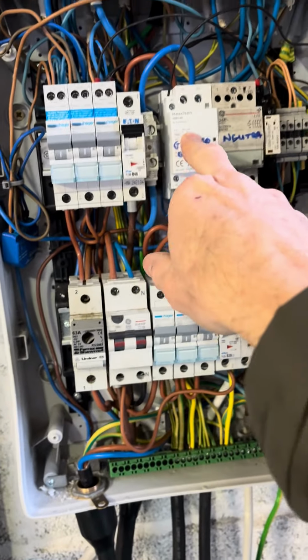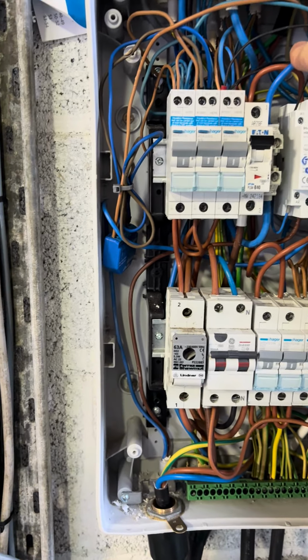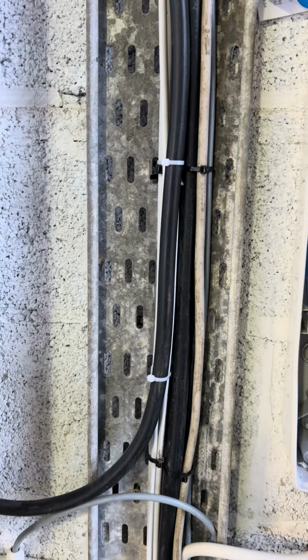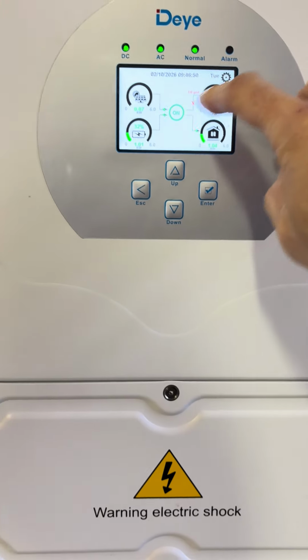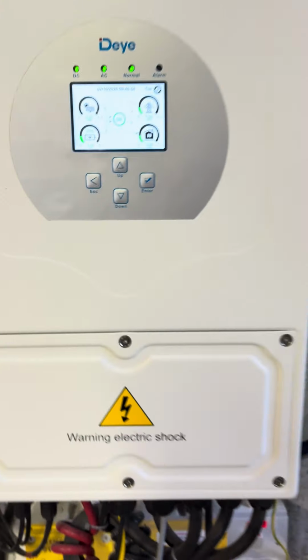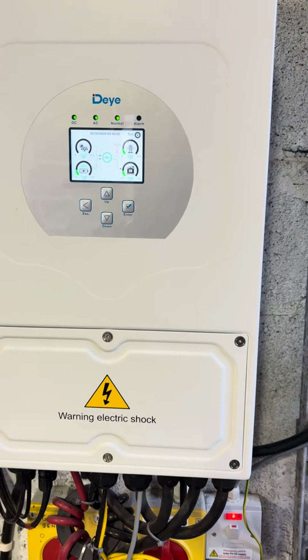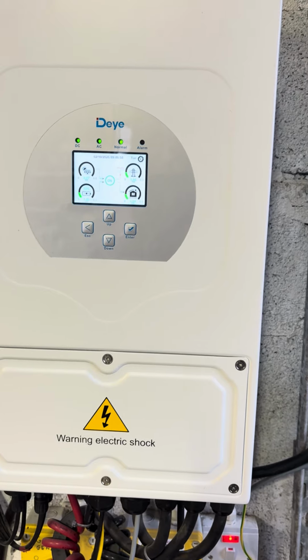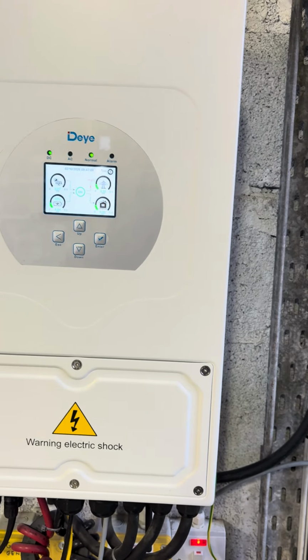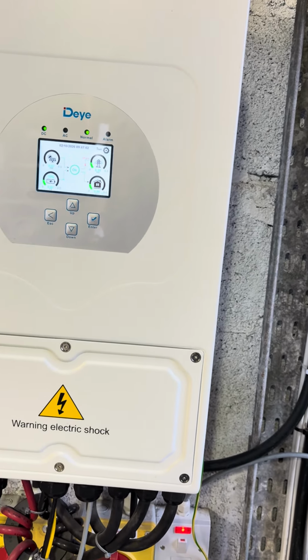Now, to get around this, what I've done is I have our generator contactor here. There's an auxiliary used in this. This will energize this contactor that breaks the feed to the Deye inverter. That means that it will no longer be able to sense the grid, or a false grid, so to say. It's feedback from the UPS terminal. So that's now on.